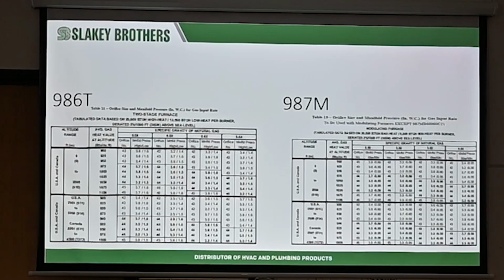But look at your two-stage. Where I'm going to get to, exact same 3.5, 3.3. But what I wanted to point out is look at the low fire rate. 1.5 or 1.4. I've been used to it for years, it's always 1.5, I'm safe, no matter what brand I ever did. 1.5 and 3.5. But on the modulating furnace, this is where a big mistake happens, and this is why units overheat, because people just didn't know. Your minimum, when you set it up for W1, 0.55. Real important right there, when you set up the low fire rate on the 987M furnace, it is 0.55 for low.